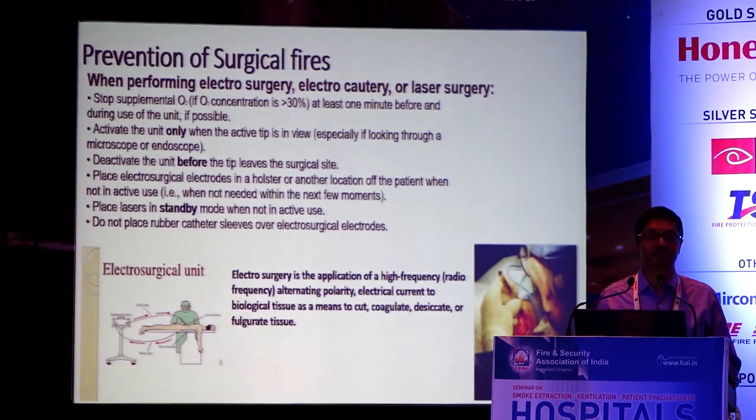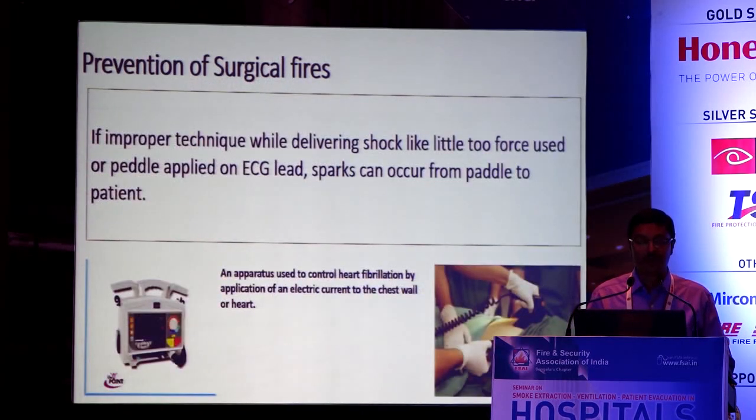Defibrillator. It may be used once in a while, especially in the cardiac OT where the patient has an arrest. When you are giving a shock, you are using 360 joules. So there is a possibility that the paddle may not be pressed properly. It may have been put on the ECG cord, so it may end up in a fire.